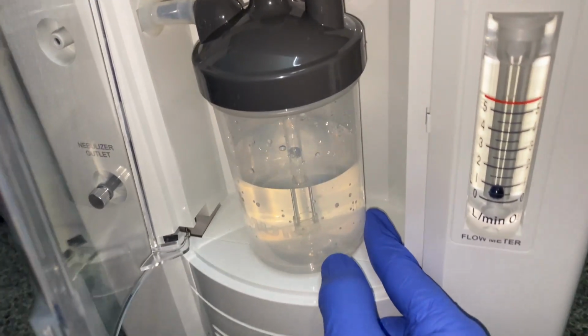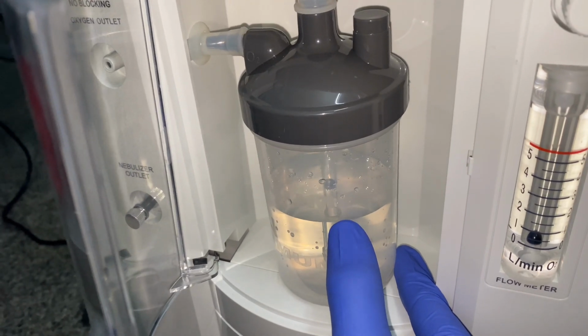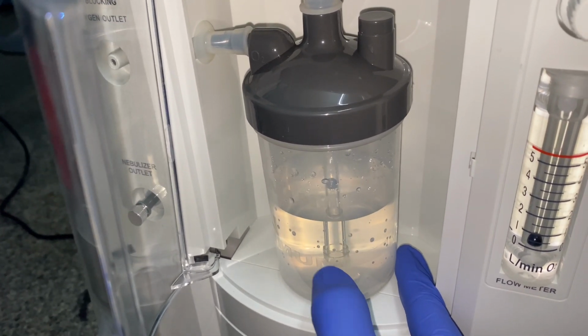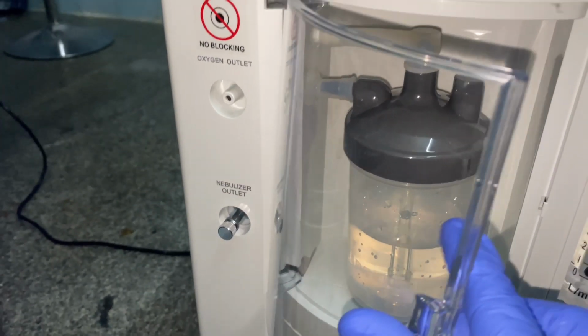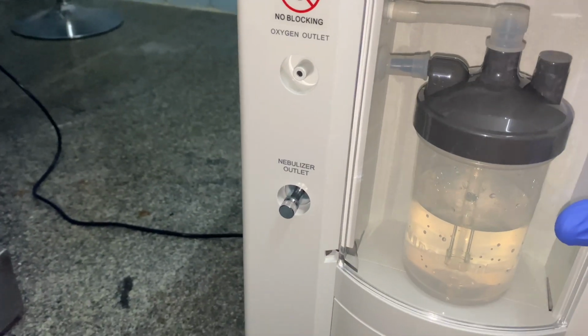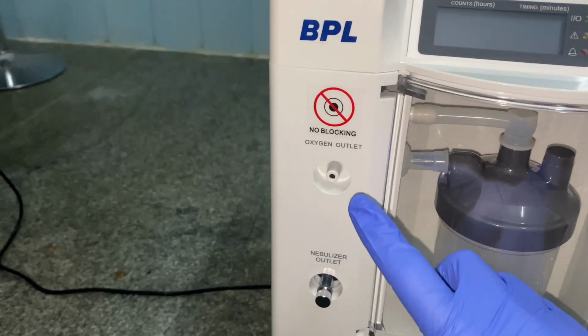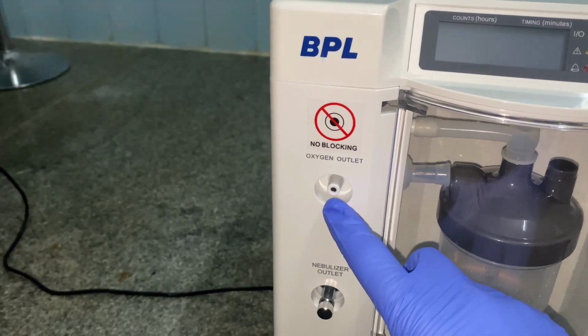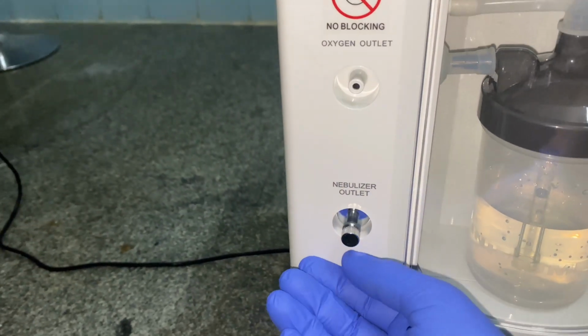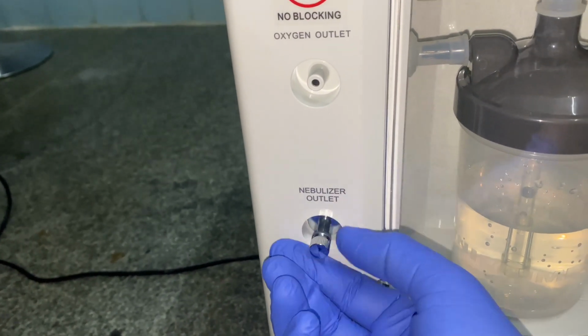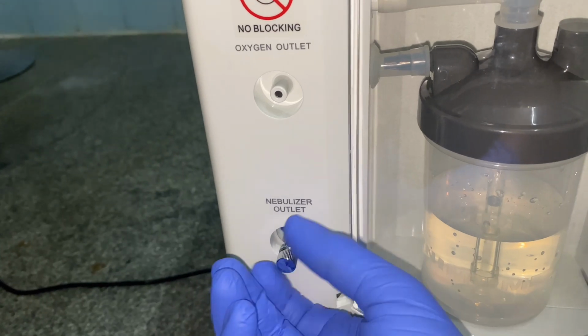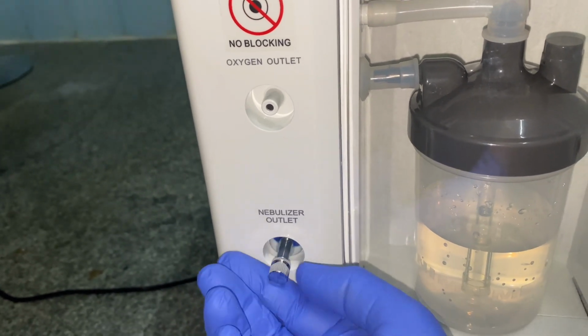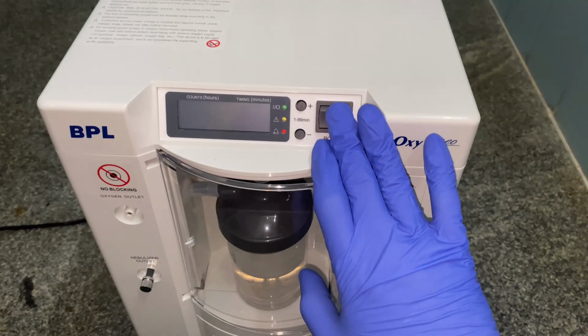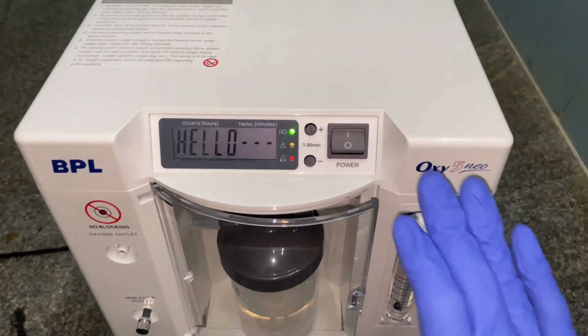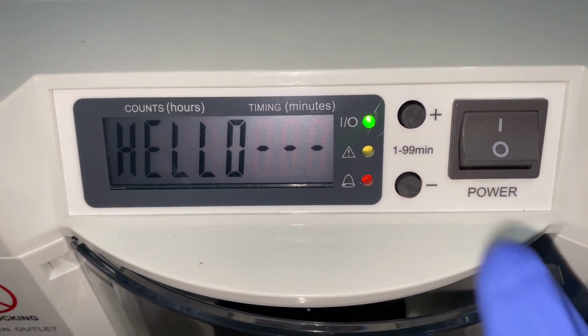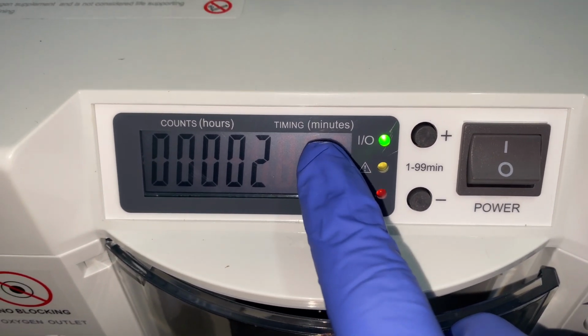Once we put the humidifier with the distilled water or else the RO water, this chamber has to be closed properly. And afterwards, we have to switch it on. This is the knob for the nebulization, which I am unscrewing now, and the upper one is for the oxygen. Once you switch it on, we get the three blinking lights. First one is green, second one is yellow, and third one is red.